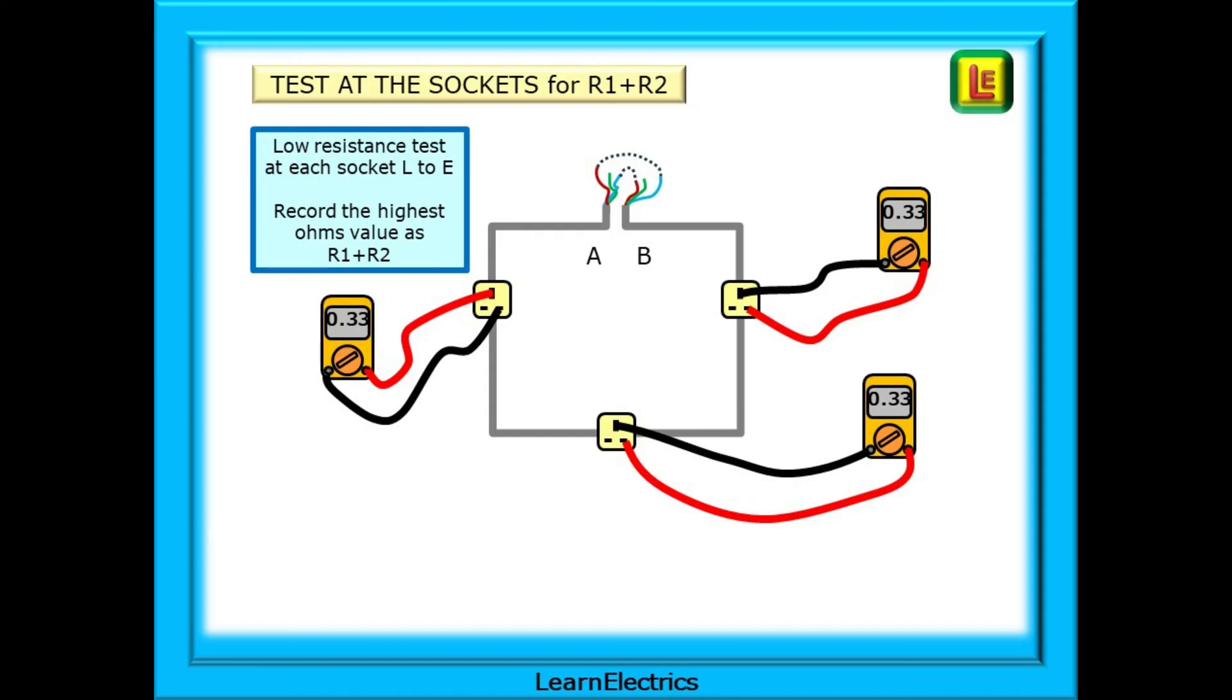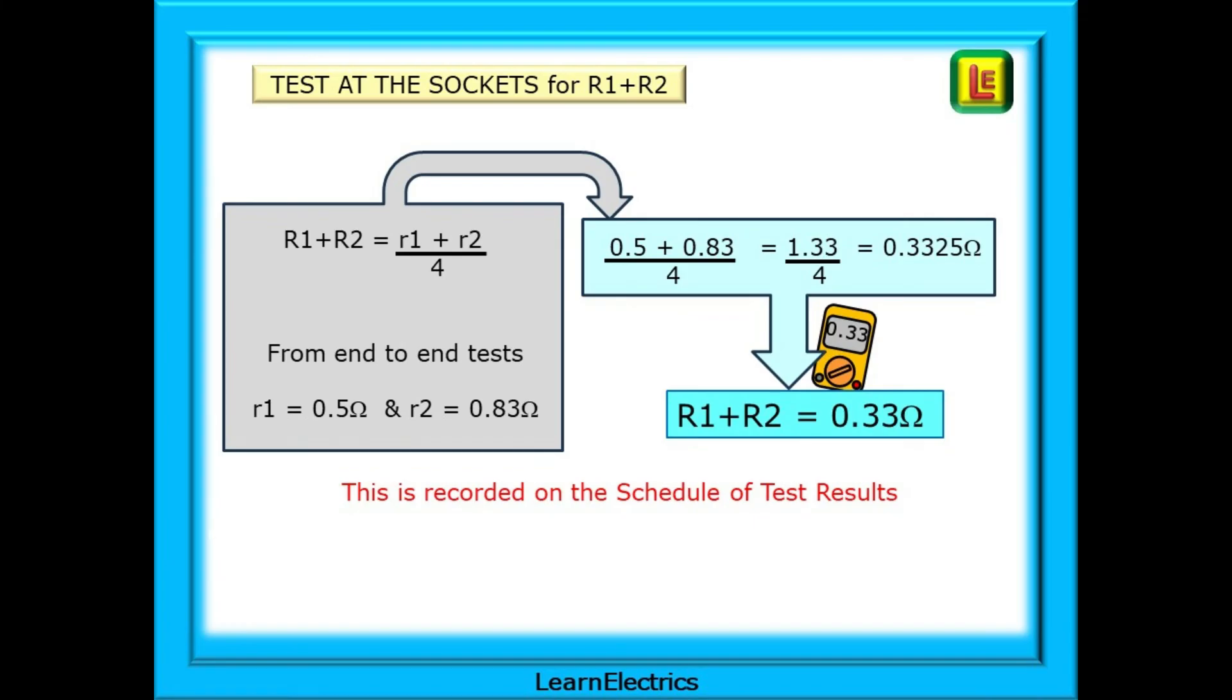By making the calculation, as shown here, we can confirm that 0.33 ohms is the test result to be expected. We already know little R1 and little R2 from the end-to-end tests, so we add these together and divide by 4. The answer, when rounded down, is big R1 plus big R2 is 0.33 ohms. If your test results are close to the calculated figures, then we know that this part of the circuit is correct.